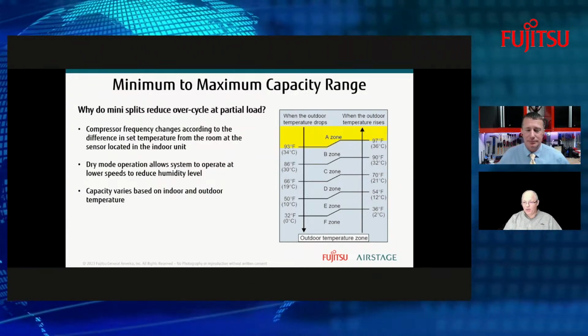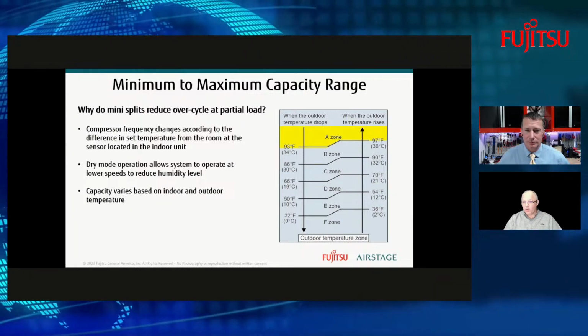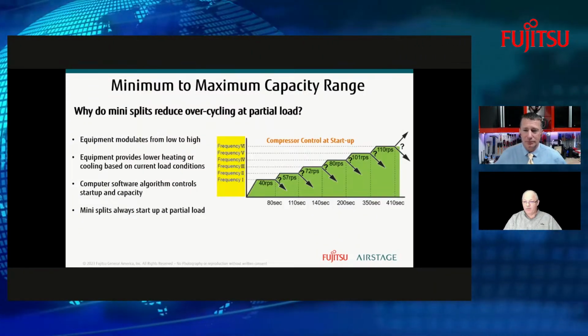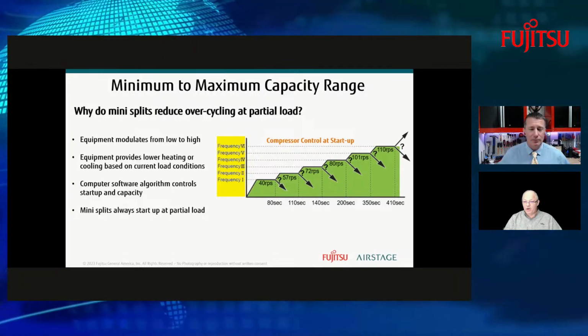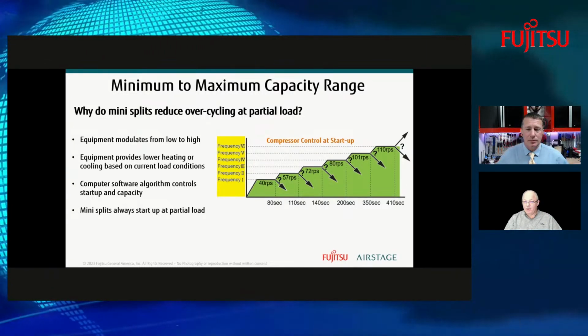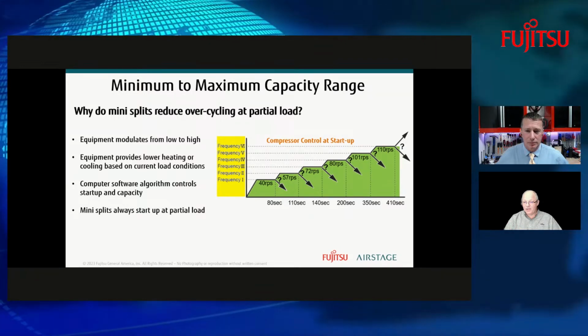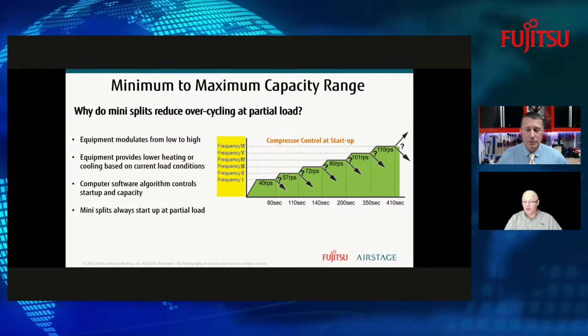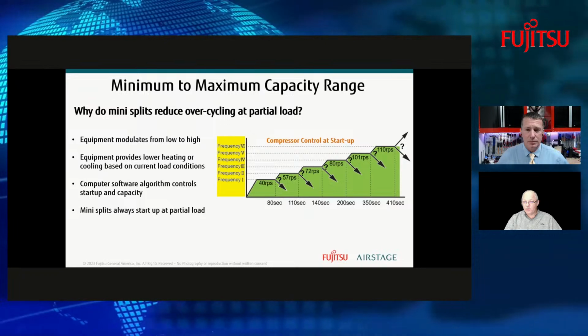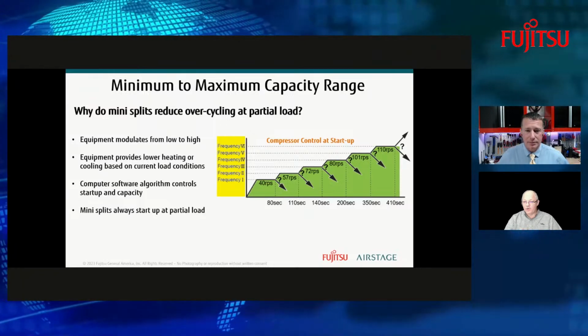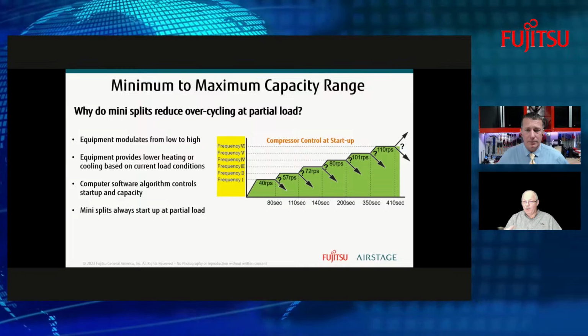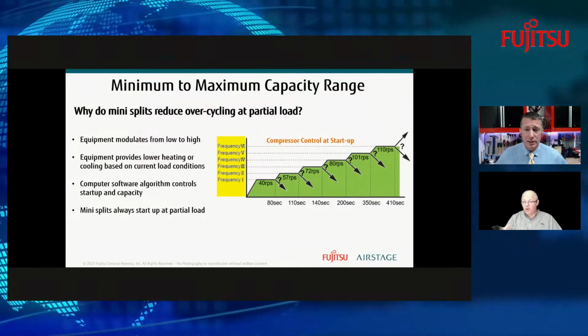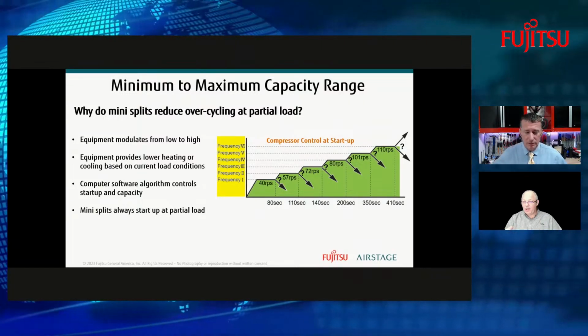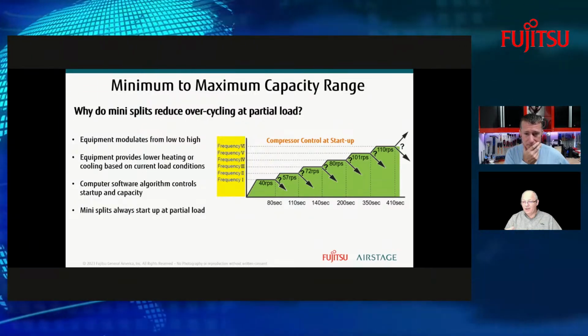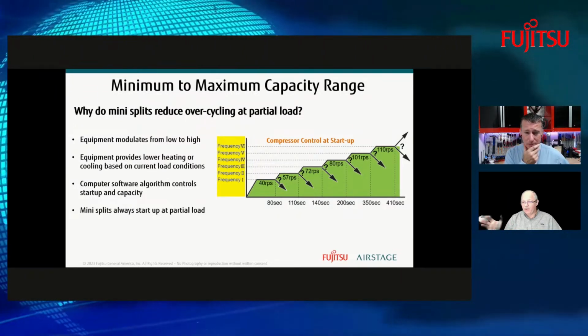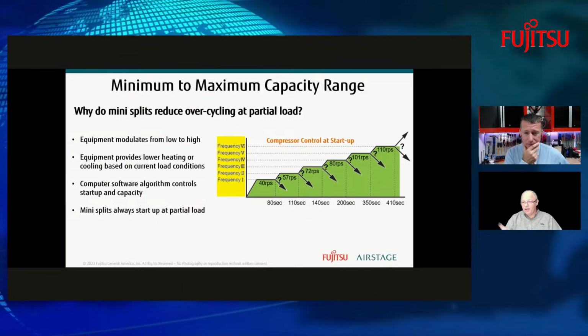It depends on whatever zone we're in here, whatever this outdoor temperature is at. That is going to determine what range we're going to run in, what speed of the compressor and what speed of the fan. When we look at these frequency ranges, 1 through 6 in this case, you can see the arrow as you go up to 40 RPS, that's where this one's going to start out. It runs for a certain amount of seconds, then it will ramp up the RPS gradually. If you can satisfy the space in 200 seconds, you don't need to go to 110 or higher. You're already on a mild day. You don't need to go to full.